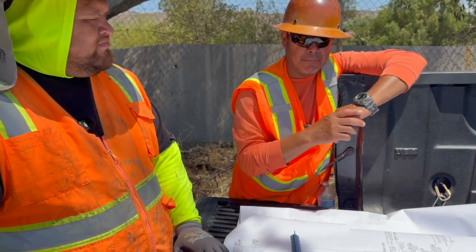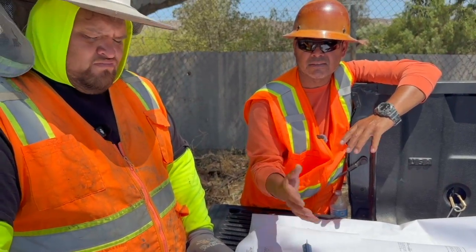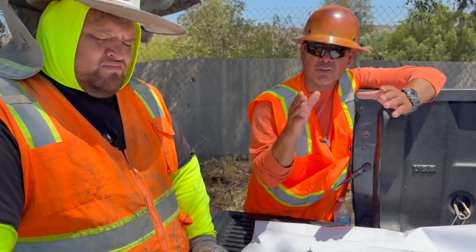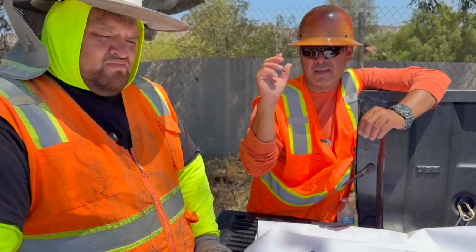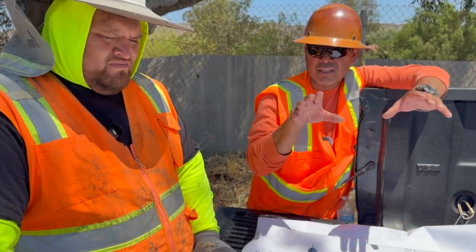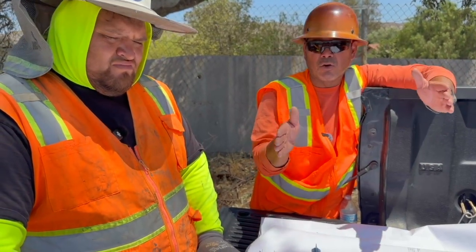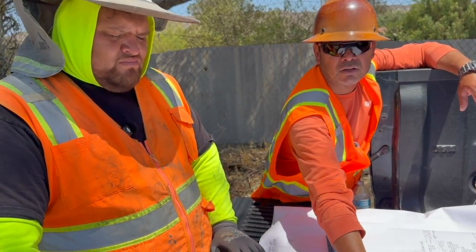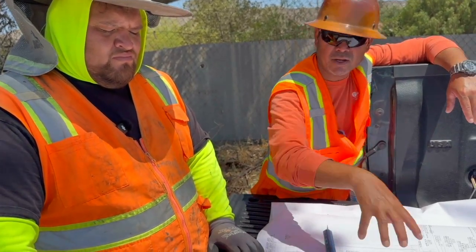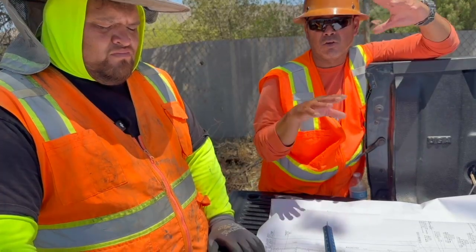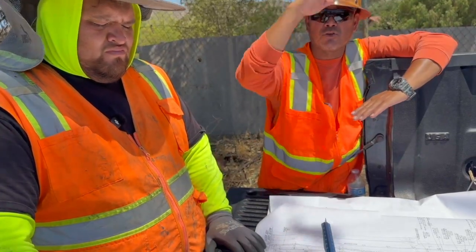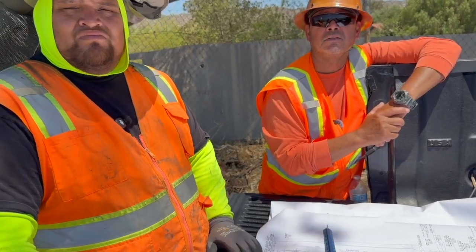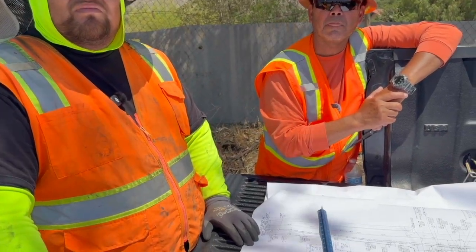Every company that provides the boxes gives us what we call a cut sheet that has all the details on the information, how high is the box, how wide, all the details on it. And that way we know if the distance that they give us is gonna work on the location. So we have to just dig the hole based on the cut sheet that tells us how tall, how wide, how long is that box. And then your next determination from there is using the stakes to tell you what your elevation is and everything?